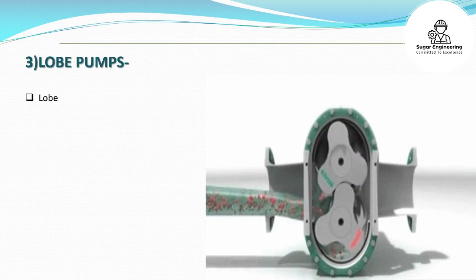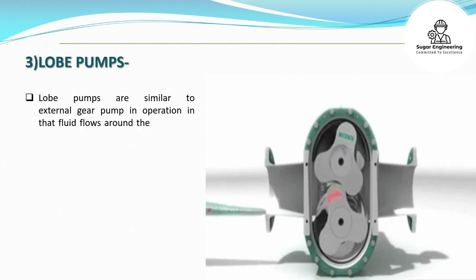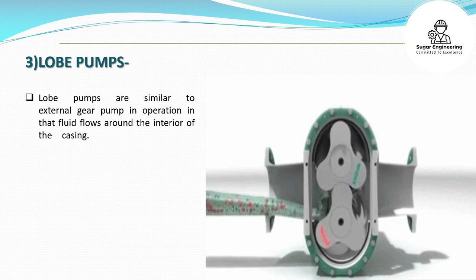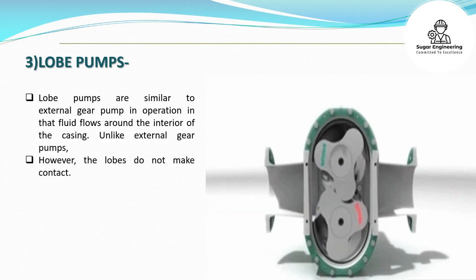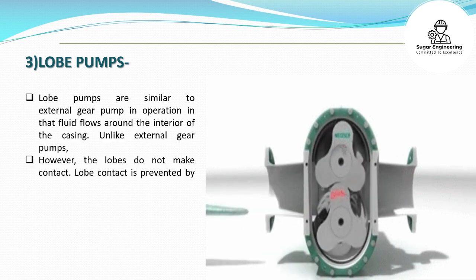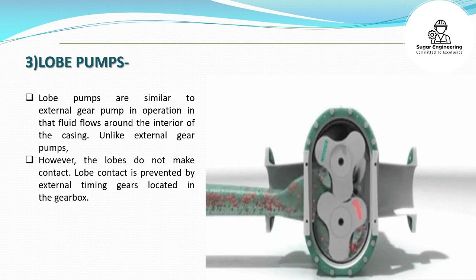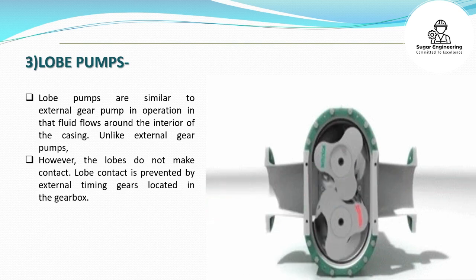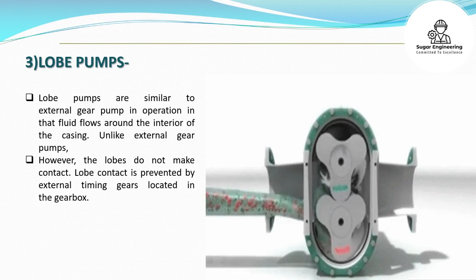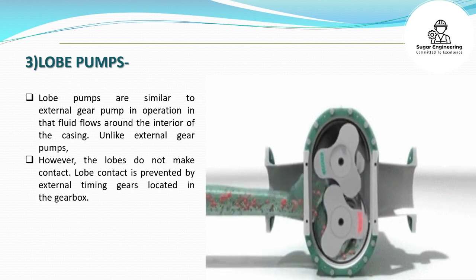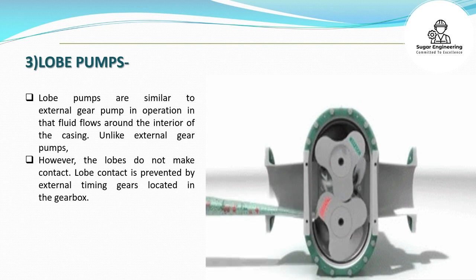3. Lobe Pumps: Lobe pumps are similar to external gear pumps in operation in that fluid flows around the interior of the casing. Unlike external gear pumps, however, the lobes do not make contact. Lobe contact is prevented by external timing gears located in the gearbox.